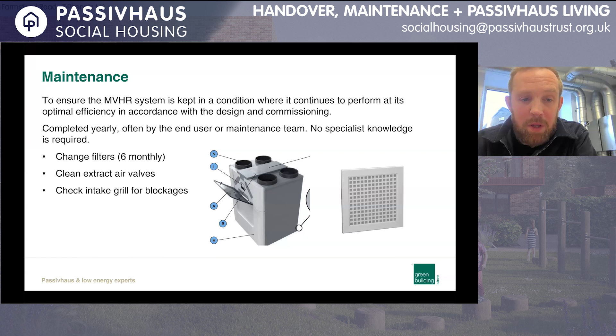So as you can see here, there's some pictures. I did have the before and after pictures in there, but you can kind of imagine what it'd look like afterwards. So as you can see on the top left picture, that is an extract valve that was in a bathroom, and that is after a year of the system running. So it doesn't take long for it to get like that. We do label the air valves, so once we've commissioned the system and set it up, we'll label them so that if anyone decorates or removes it, they know where it goes back in. And that is completely normal. That just needs wiping off and putting back in.